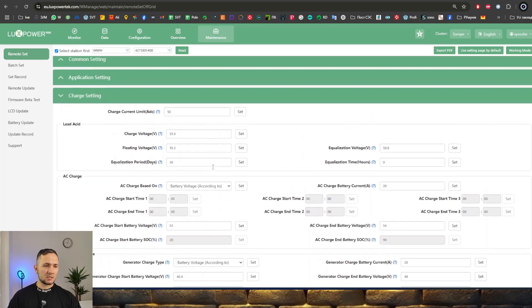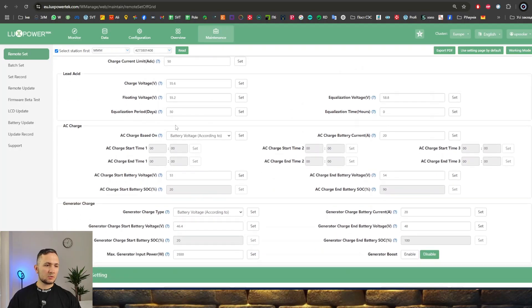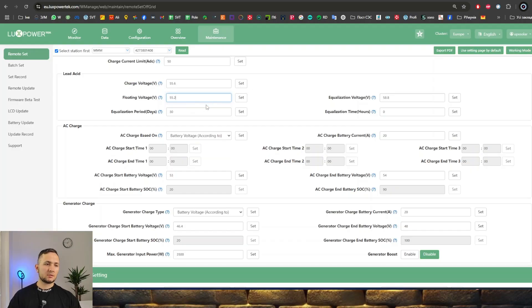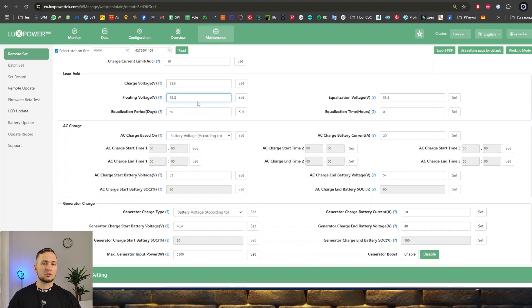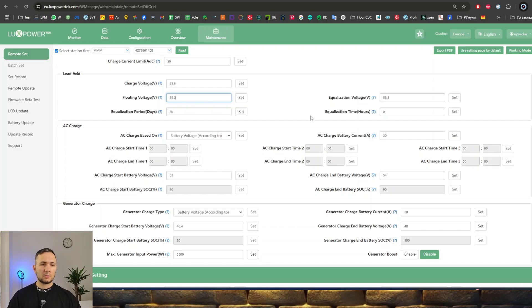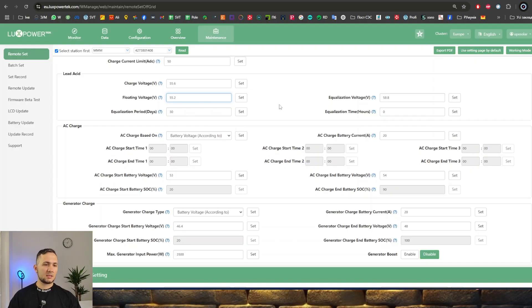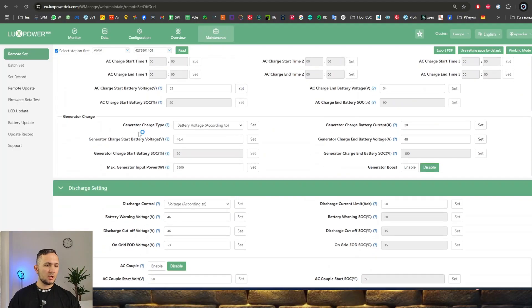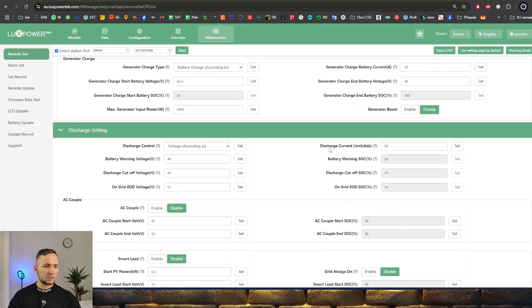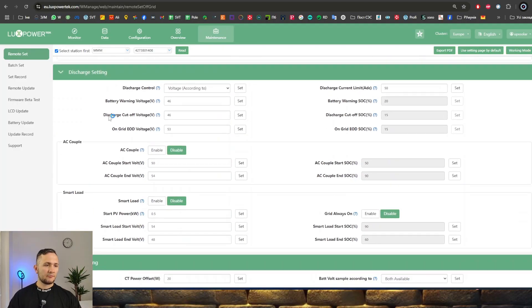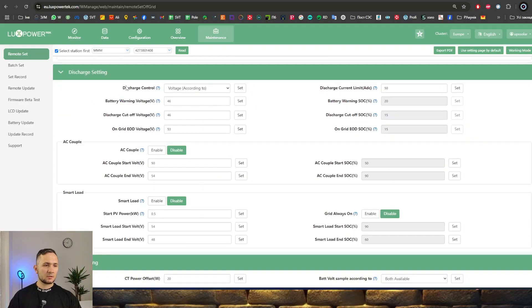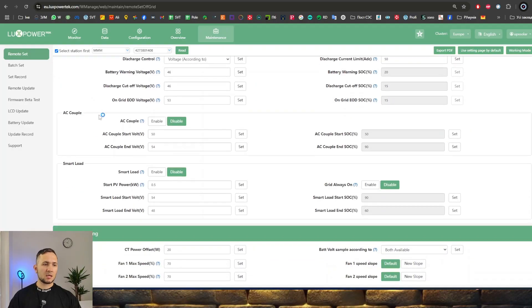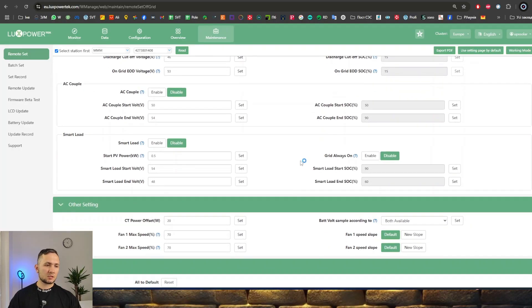Charging settings is available to switch not only charge voltage but floating charge. It's very necessary to be able to choose the correct number for exactly your battery when using batteries that don't support CAN protocol with the inverter. Equalization is disabled because lithium batteries have their own balancing system and don't need to be equalized. Here we can also see AC charge and generator charge. For discharge, we can see not only discharge control but AC couple and smart load as additional options.